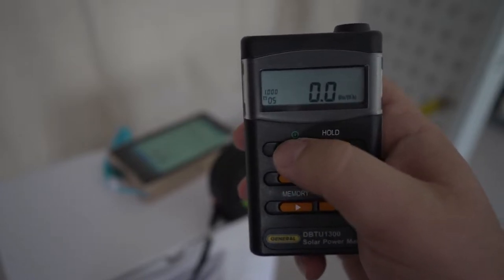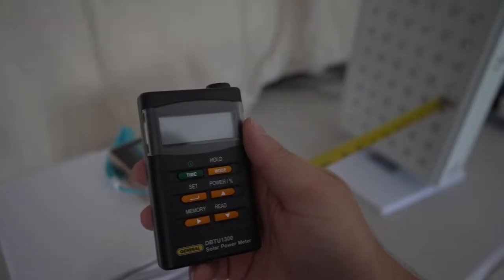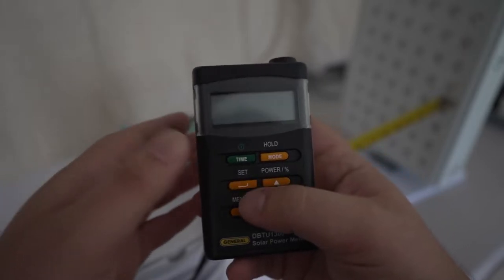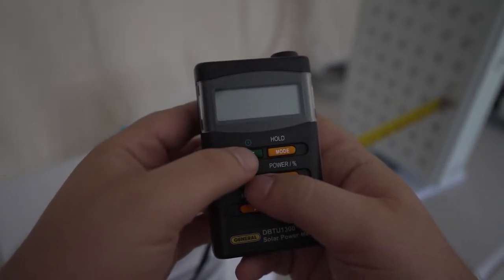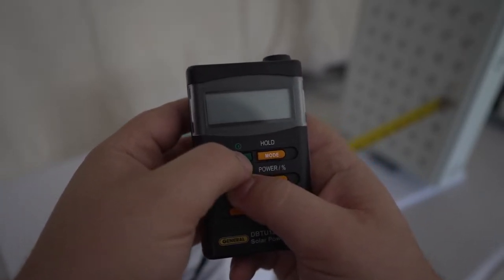The first thing you do is actually make sure your device is off. So to change the calibration, while we're turning it on, we're going to hold this set button, and then we're going to turn it on at the same time.